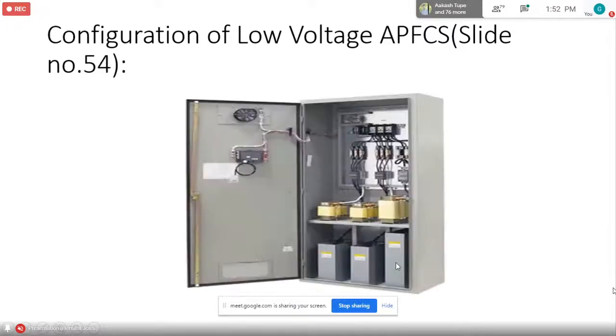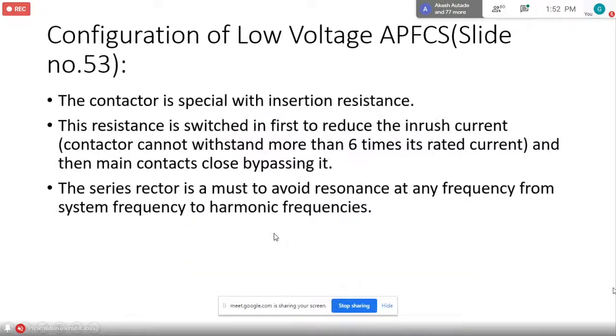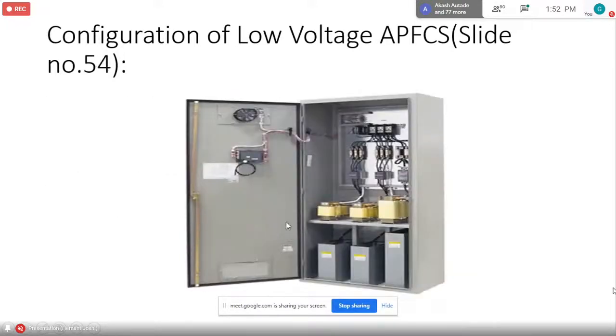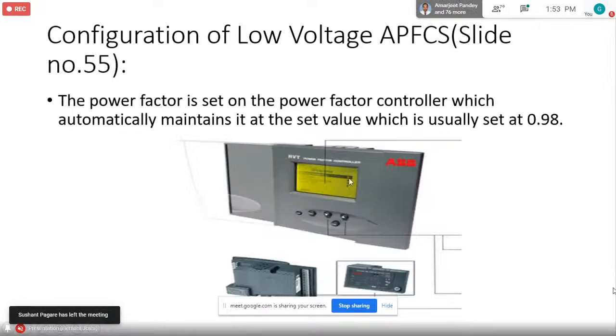All right, this is how it looks. These are the kVAr banks. This is the series reactor, and this is a contactor, fuse. As I told you, you can have an MCCB instead of a fuse. This is not a good design because he hasn't provided the isolator. Never ever do that. Always have an isolator, because if you have to work on the capacitor, you can isolate it. Pulling out a fuse is not a good idea. All right, this is the power factor controller, and you press the button and set the power factor on it.